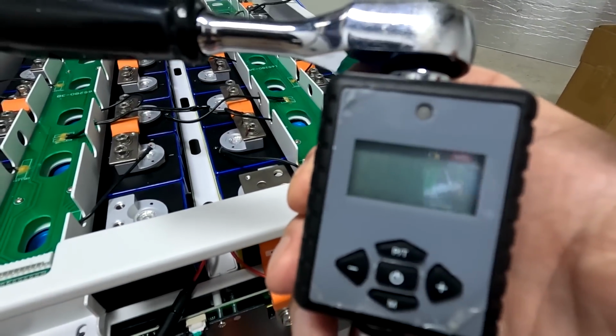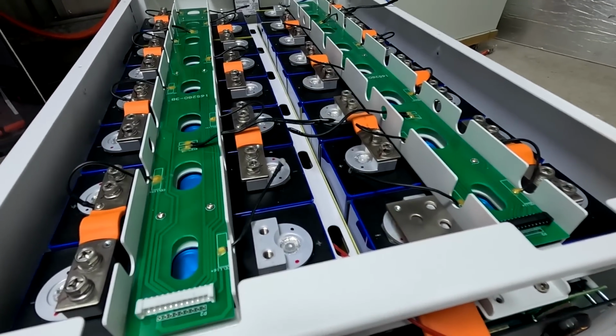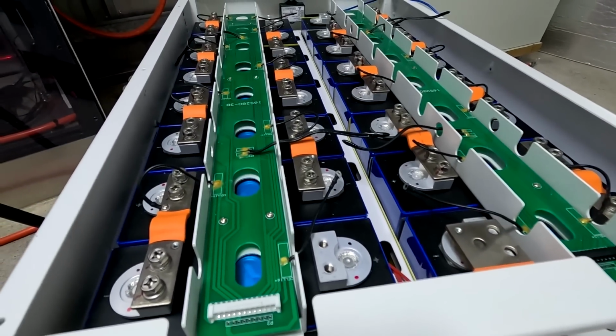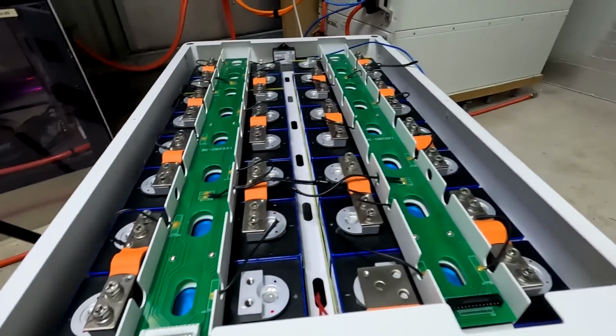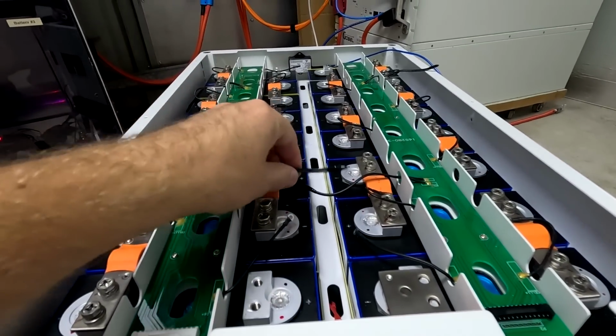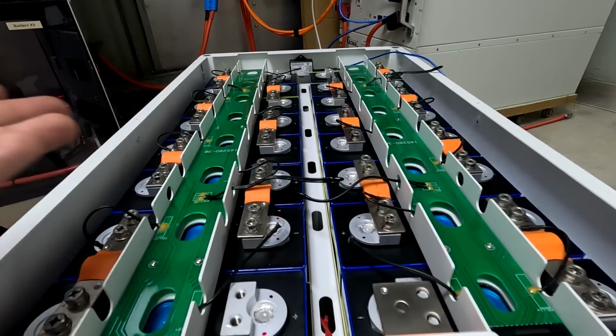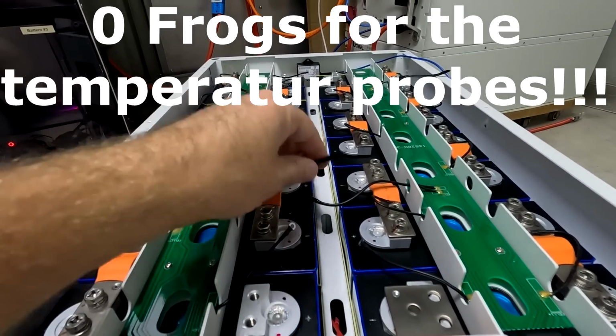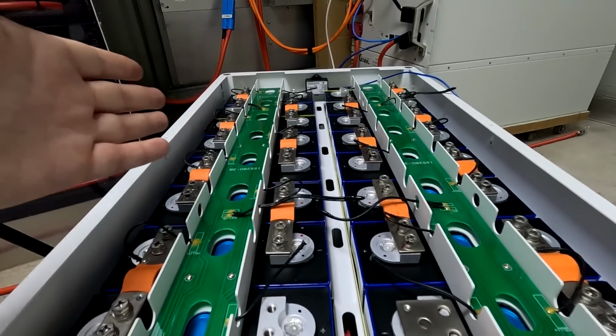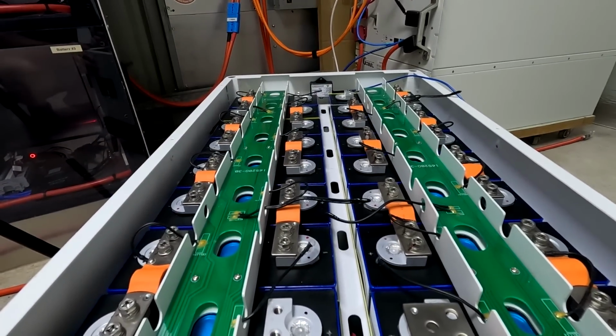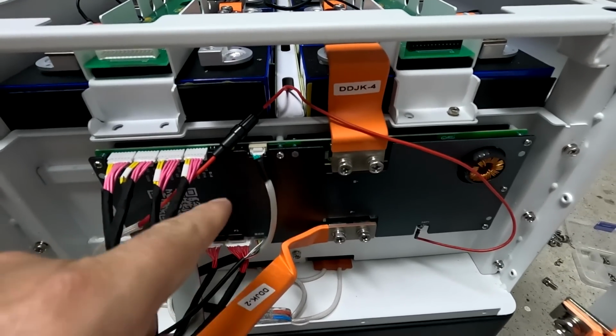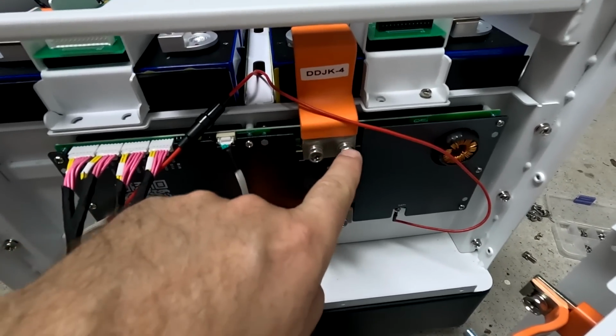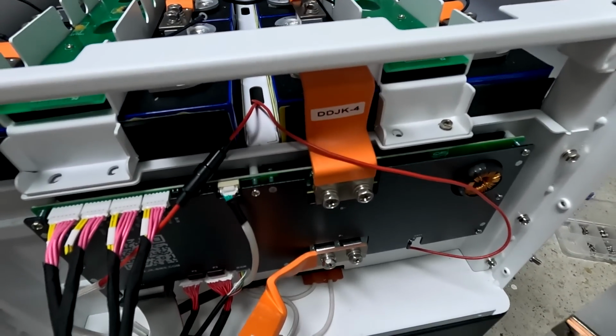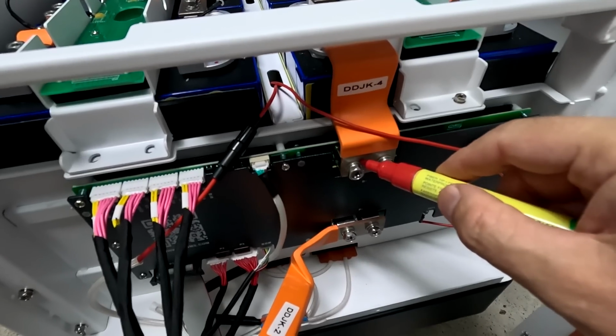So I've now torqued all the screws of the terminals here with 4 Newton meters as always, and marked them all off as checked and torqued. I connected all the balance cables, and left the temperature sensors hanging in the air because there's no other way - I don't like this situation. What are they measuring? Air temperature inside the box in 4 different corners - makes no sense. I mounted the JK Inverter BMS here, torqued these ones with 4 Newton meters, and I need to mark them off because I torqued them just now.